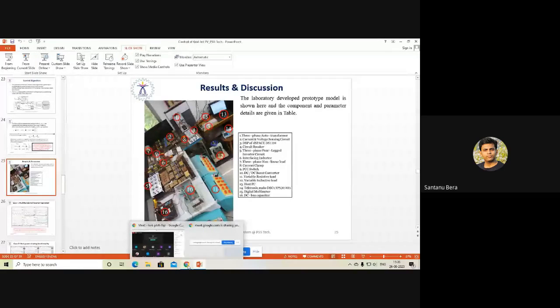Sir, I asked what is the actual function of the active power filter and why it is used. The voltage at PCC must be constant, and moreover the grid current injected into the utility grid must be sinusoidal. So you are using an active power filter to mitigate the harmonic component present in the source current. Whenever you connect a three-phase non-linear diode rectifier load, the current never follows the voltage. There is a strong non-linearity between voltage and current, so it distorts your supply current. If the supply current is distorted, whatever other loads you connect to the same supply will ultimately be affected. For example, if you connect an electric oven, you can find overheating due to the harmonic component. So that harmonic current has to be neutralized, and that is why we use an active power filter, which injects a complementary component of the harmonic present in the grid current.